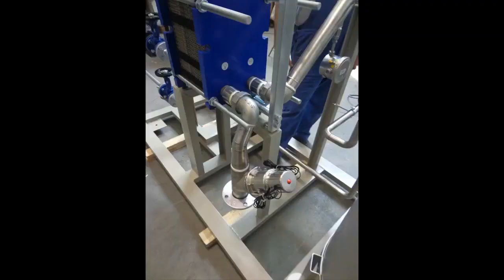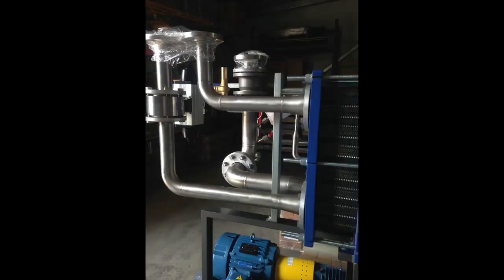What's the trick? Putting 90-degree curves and bringing the valves out beyond the shape of the heat exchanger. This way, when we do maintenance, we intercept the valves, disassemble the curves, and can easily move the rear barrel to open the exchanger, wash the plates, and replace the gaskets. After the operations it's closed, the curves and valves are reassembled, the circuit is opened, and the job is done.